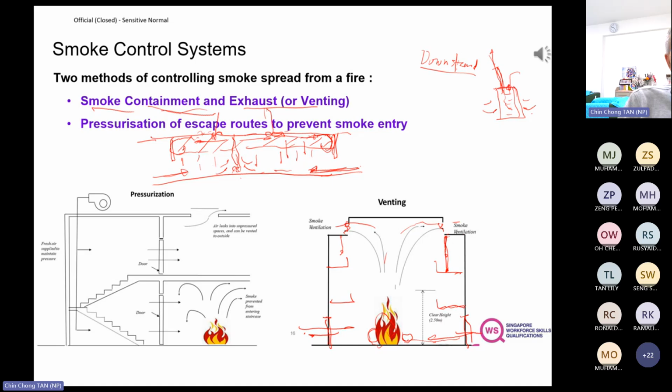Okay. Now, just now the gentleman who said that above the fire floor, he's correct, no? If there's a fire here, you cannot have the smoke curtain roll down from the fire floor because otherwise, where would the smoke go, right? So the one above the fire floor will prevent smoke from going in and going through, okay? However, if it's in the atrium, then all will come down. But it won't go all the way, lah. That's what I'm trying to say, lah. Huh?